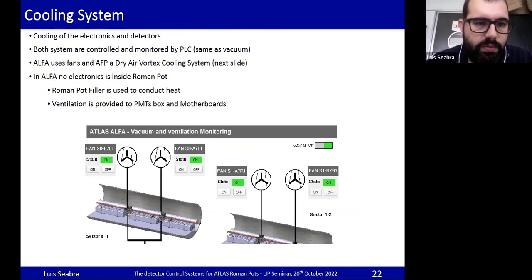So for the cooling system, we use it to cool our electronics and the detectors themselves. Both systems are controlled by the same PLC used for the vacuum. ALFA uses mainly fans, and AFP a system called the dry air vortex cooling system, which I mention in the next slide. ALFA doesn't have any electronics inside the Roman pot, so we use a filler that will conduct the heat to outside the Roman pot, and the ventilation is provided for the PMT box and the motherboard. From the previous panel, I'm just showing here the part that is responsible for the vacuum and ventilation.